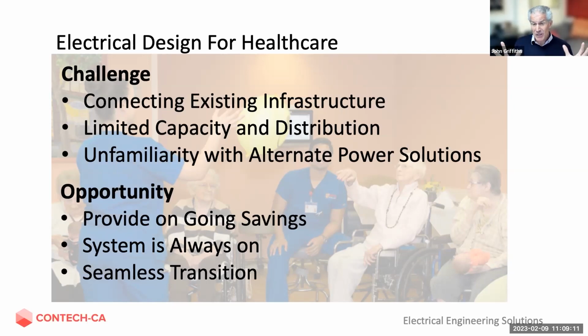The other one is a seamless transition. A generator is great, but you have up to 10 seconds until the generator starts and transfers, and you lose power. It depends when it happens, but in that 10 seconds, from my experience being in facilities when testing or losing power, it can be somewhat disruptive.